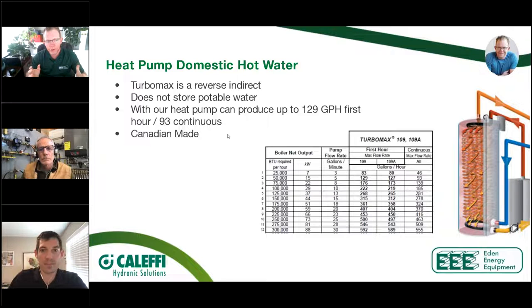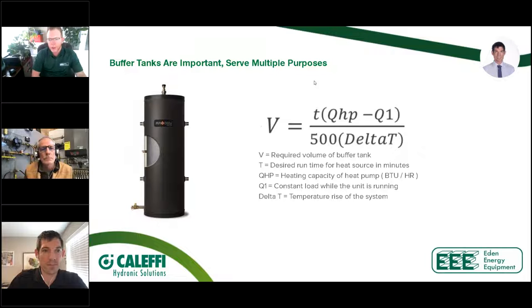So we've just got this up here. This is a reverse indirect, and what it is, it's actually not storing potable water. It's storing the actual heat pump water. But again, we've got other training modules where we touch on this. The big thing is we just want you to understand this is not a standard indirect. Don't put indirects on heat pumps, whether it's a water to water or an air to water.